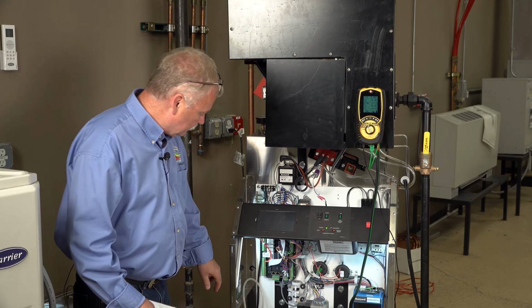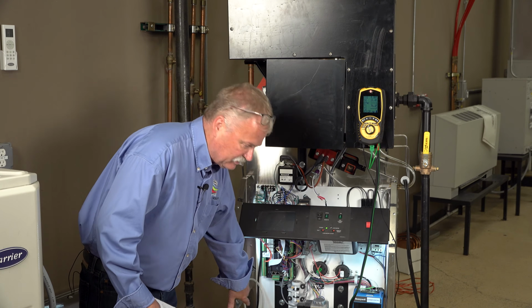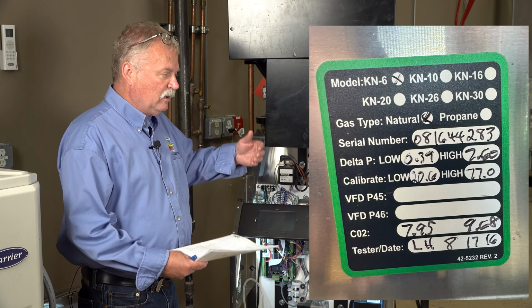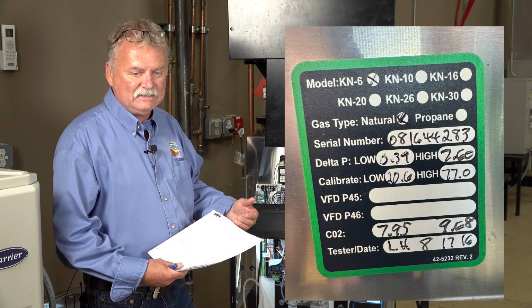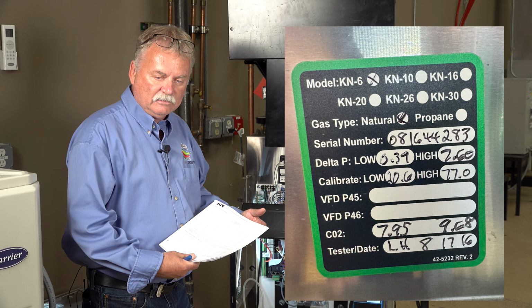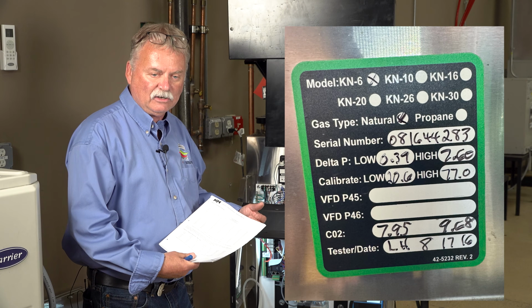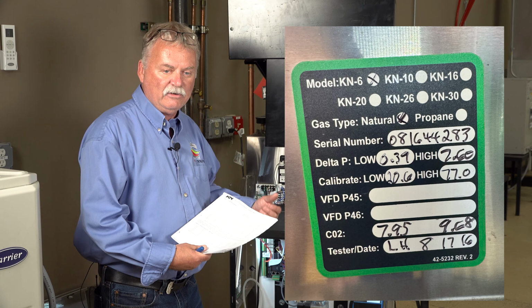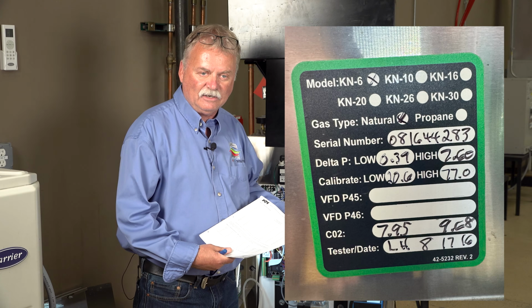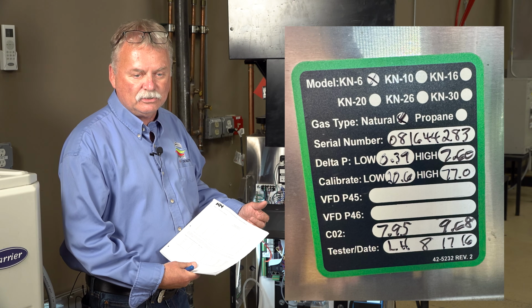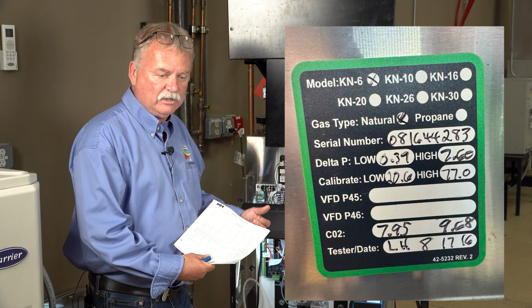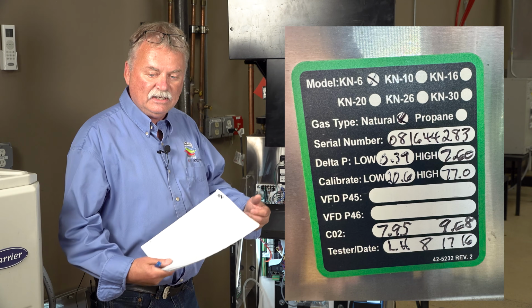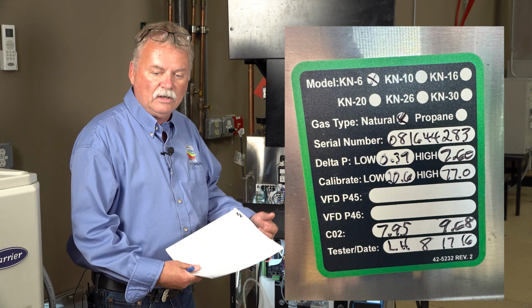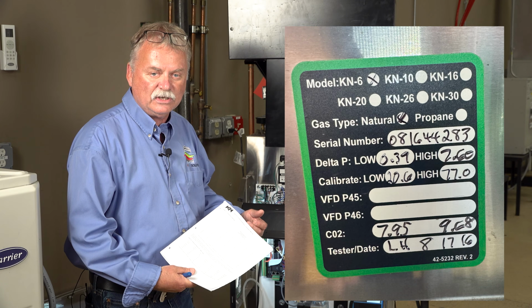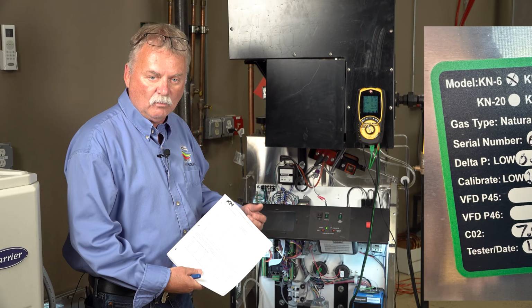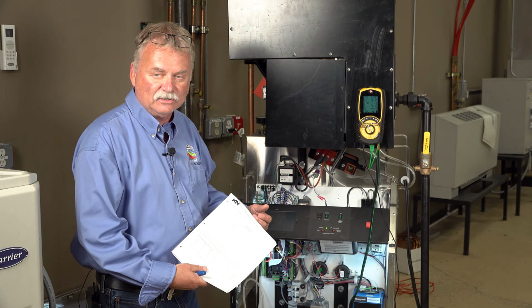Also in this boiler, it's hard to see, but we'll show you later, there's a tag in here from the manufacturer. Most high efficiency boilers are tested at the manufacturer to make sure the combustion is set correctly. That is going to vary from state to state. This boiler was manufactured in Massachusetts, and we're here in the Chicago area. The gas is a little different. So that's why they want you to readjust and check your gas pressures and your gas combustion settings when you get it on site to a live application.